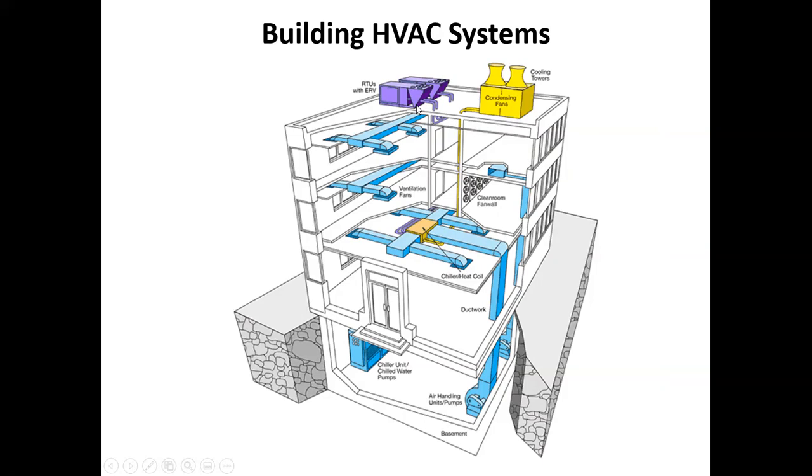Well, when we look at ASHRAE 62, it's going to require someplace in the range of probably 10 CFM per person, at least, of ventilation air. So let's just say we had 50 people times 10, that's 500 CFM, and that's just in this space. So if you had a good size RTU doing this end of the building, it might have 5,000 CFM of outside air.